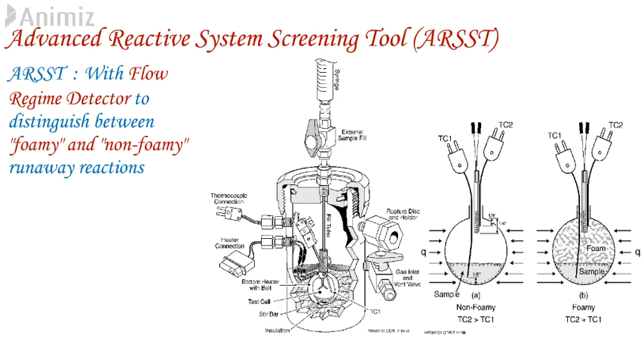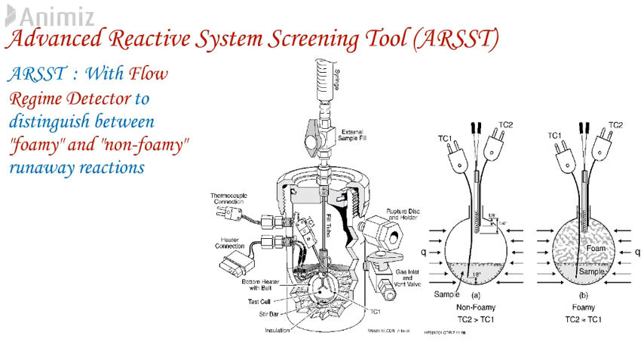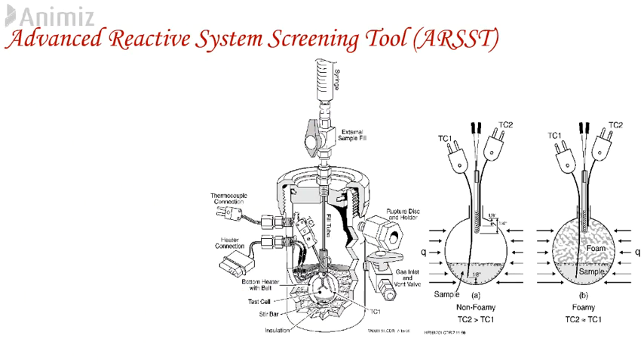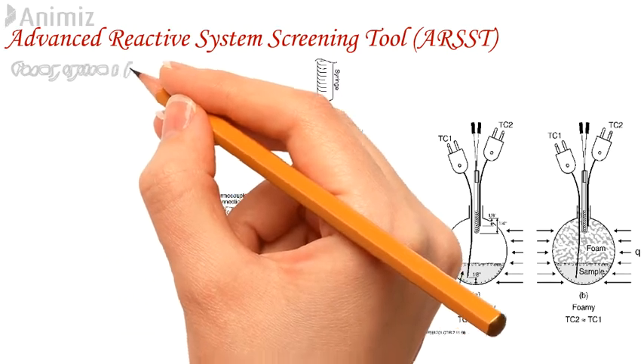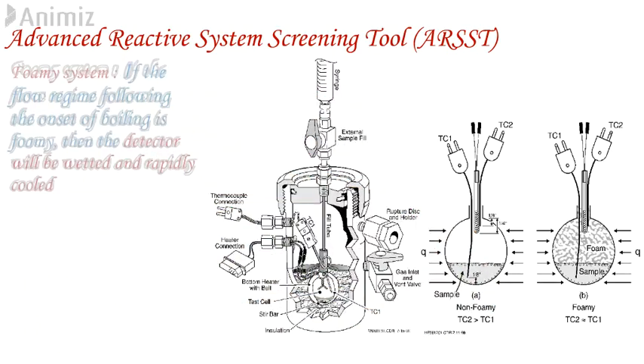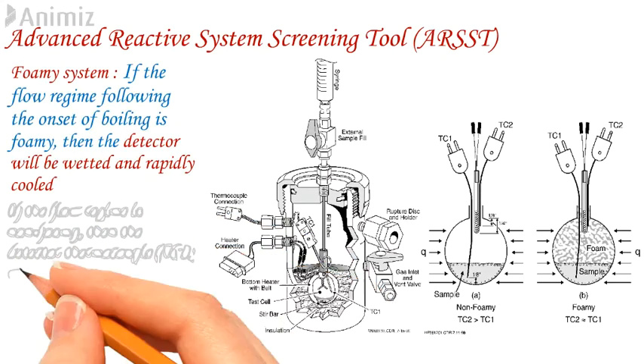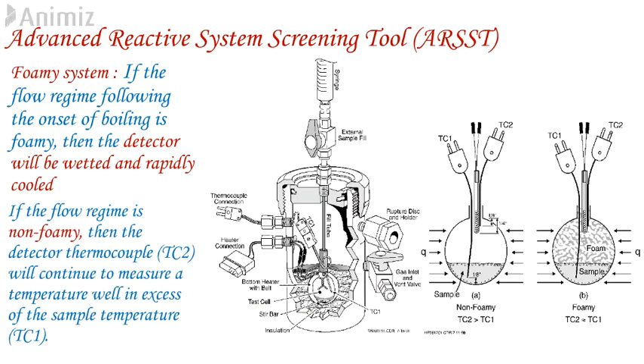The detector temperature is displayed on the ARSST screen and logged to the output data file. Prior to externally heating the chemical sample, power is supplied to an internal heating coil to establish an elevated sensor temperature well above the anticipated boiling temperature of the sample. If the flow regime following the onset of boiling is foamy, the detector will be wetted and rapidly cool. If the flow regime is non-foamy, the detector thermocouple will continue to measure a temperature well in excess of the sample temperature. Relief systems for non-foamy systems may be more realistically designed by treating two-phase flow discharge as churn-turbulent rather than homogeneous.